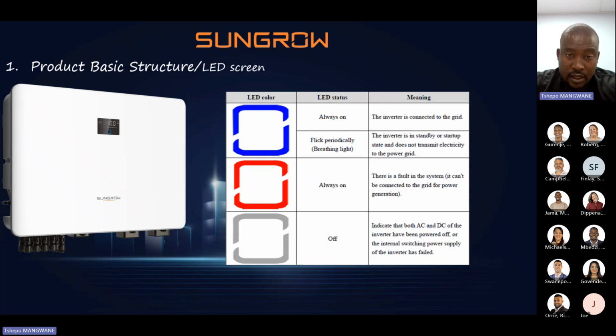All right. Red indication, just know that the inverter has a fault mode, whereby we need to start doing our troubleshooting according to the fault code. It could be grounding detection, it could be arc fault detection, which is caused by a loose connection, or a wrong connection on the terminal side, on your polarity side, on your batteries. The last one is grayed out, or maybe white. Some people will see it as white, but it's gray. Just know that the inverter is completely off.